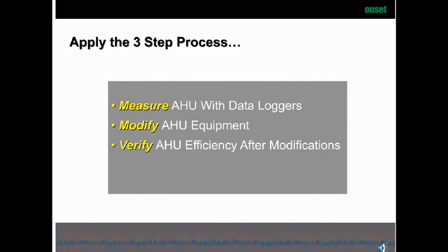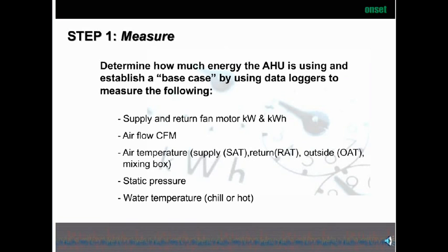So in an air handling unit, here are the three steps we want to follow. First, measurement — we can measure the AHU with data loggers to determine how much energy it's using prior to making modifications. From that data, we can determine the steps needed to correct issues, make the modification, and then verify that the modifications were effective. Let's determine how much energy the AHU is using and establish a base case using data loggers.